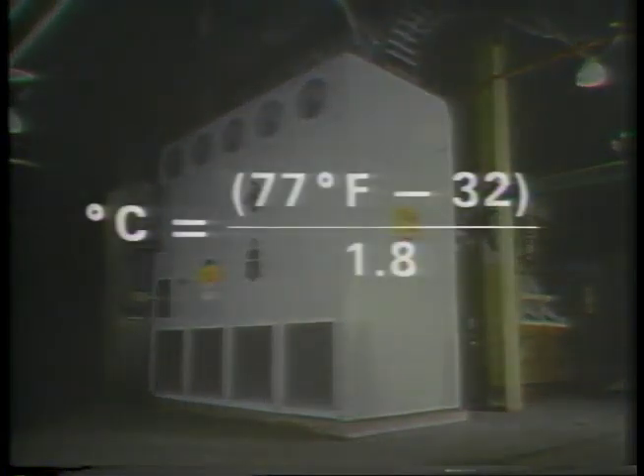The equation is 77 degrees Fahrenheit minus 32, divided by 1.8. This equals 25 degrees Celsius. We can now find the difference between the transformer temperature and ambient temperature, which is 60 degrees Celsius minus 25 degrees Celsius. The difference is 35 degrees Celsius. Now, this tells us that we can normally expect the difference between ambient and transformer temperature to be 35 degrees Celsius, as long as the load on the transformer remains the same.